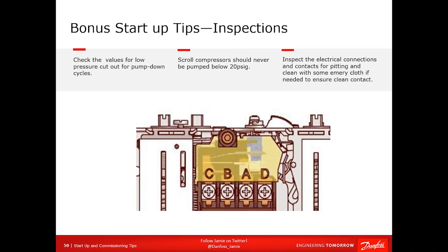Finally, check your pressure controls. Make sure they trip. There is a test button on the Danfoss KPUs. You just push the reset button on manual reset. If it's auto, don't bother. Hit the test button and you will move the contacts.